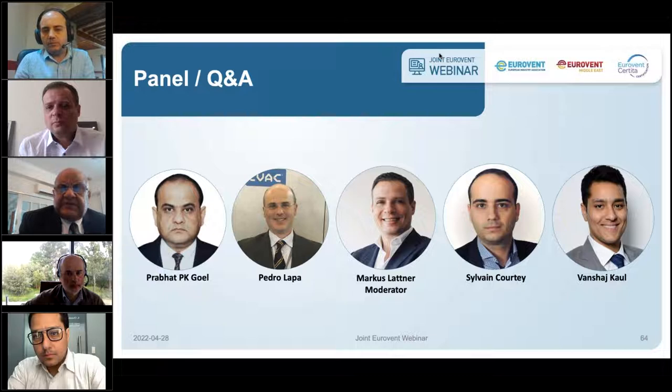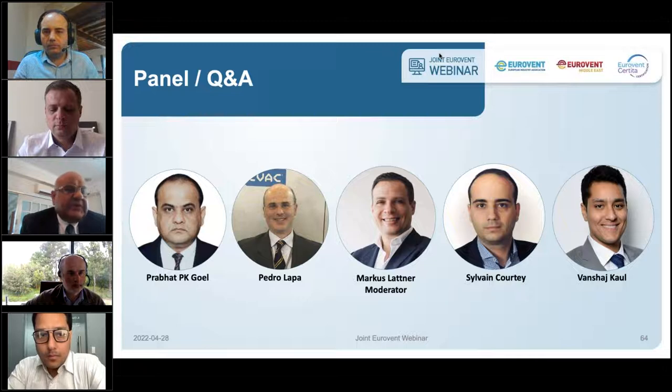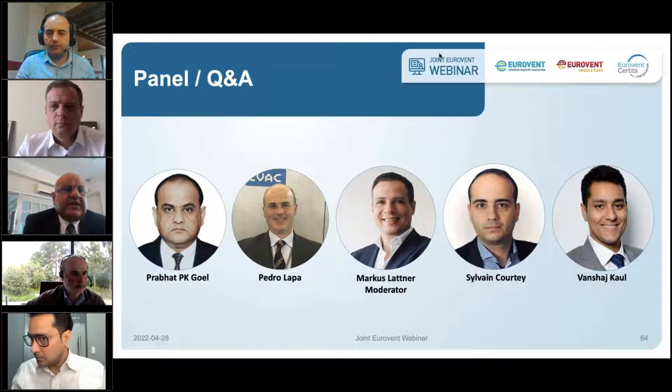Okay, so I visited Jeddah on certain occasions where air handling units were right next to the sea, as humid as it gets. One of the things we noticed on one of the sites was moisture on top of the unit itself, and the design was done correctly. But there were fan coil units installed in the air handling unit room to first remove the moisture around it, and those were not switched on. So the U value, the thermal transmittance, becomes very, very important in units which are kept offshore.